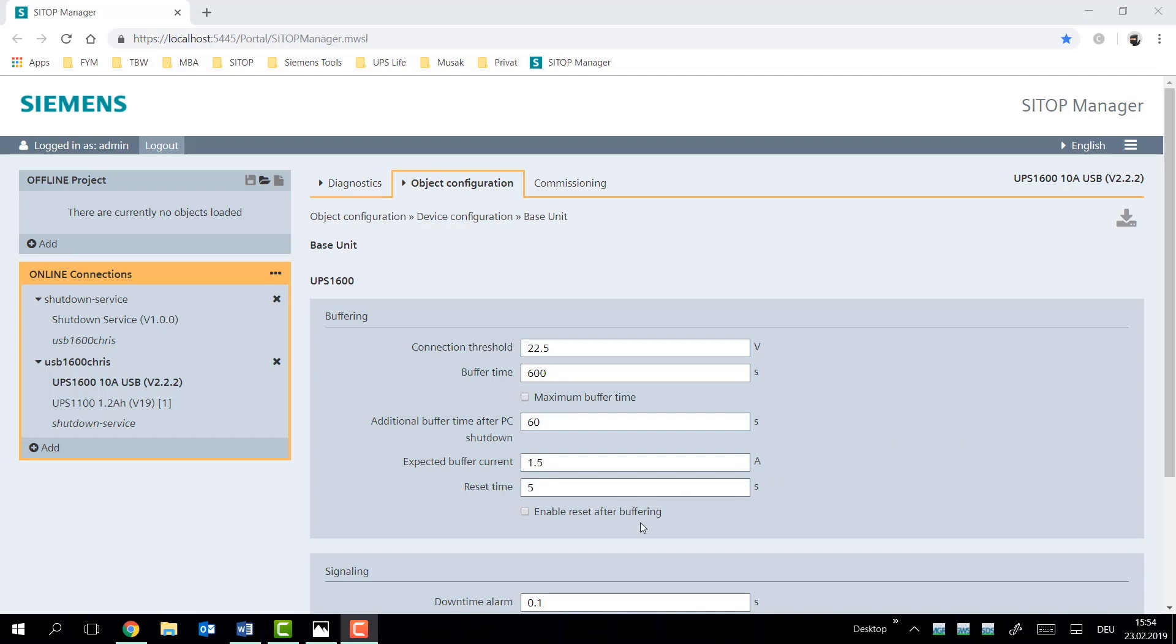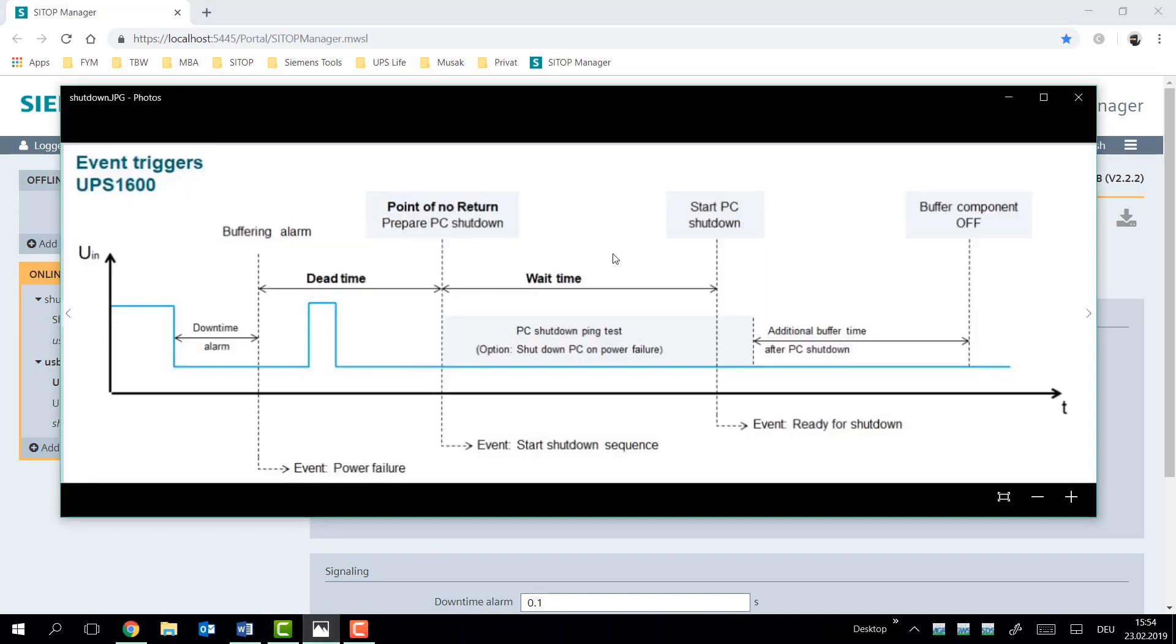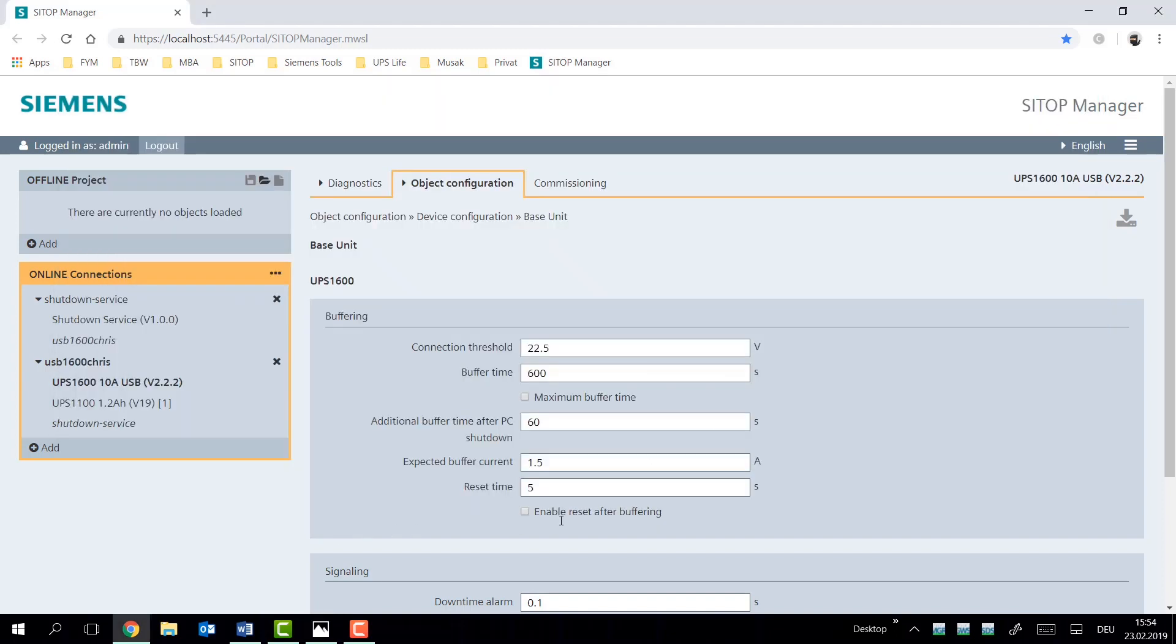Reset after buffering option is important for customers with PC applications. And this is because if we look towards the shutdown structure, once the PC has been issued a shutdown command, the only way to turn the PC back on is by cycling the output of the UPS. And that's because PCs only respond to a flanking edge at their input. To enable this cycling, we have to enable the reset after buffering option for the UPS1600. We also have additionally the ability to set the reset time necessary for the flanking output.